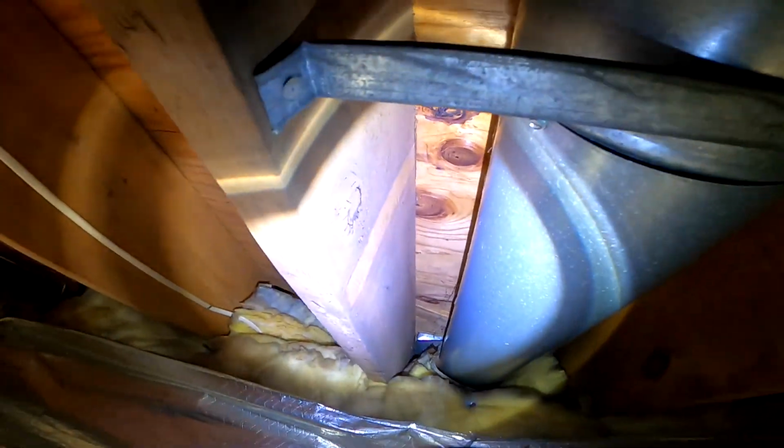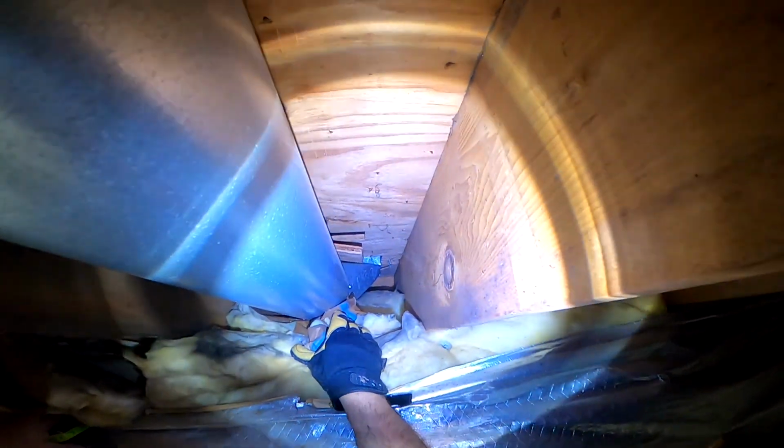And when I climb up there and poke around at the insulation, I want you to notice a couple of things. One, the overhang creates a cavity or a bay. And the second thing is that the insulation is discolored in several areas. And the thing to keep in mind throughout this presentation is that discolored insulation, dark spots, is a telltale sign that air is moving right through the insulation.